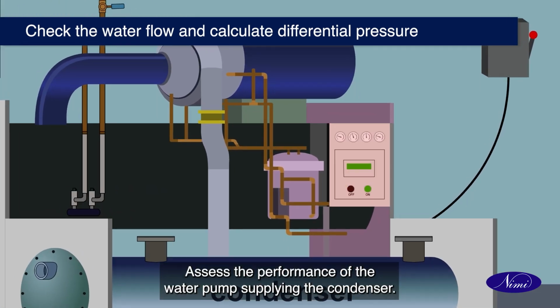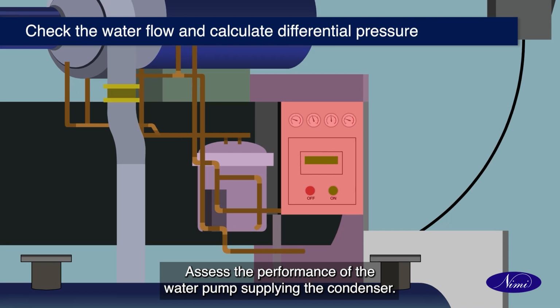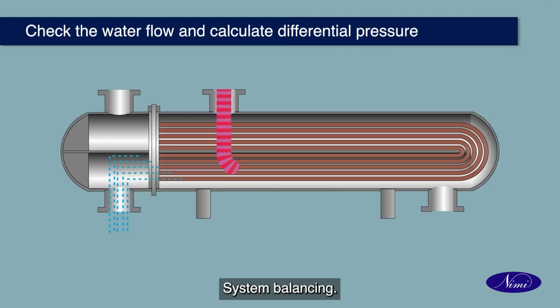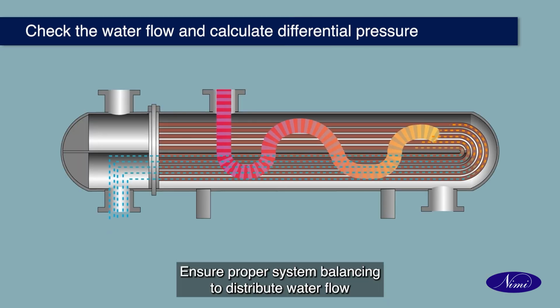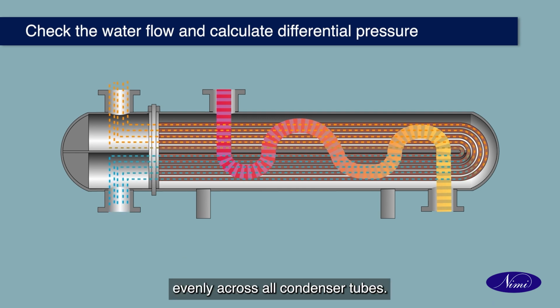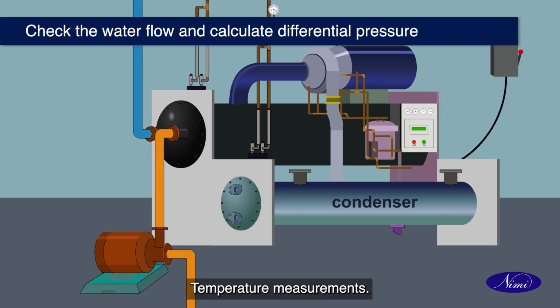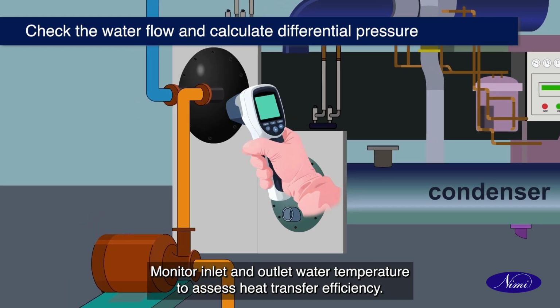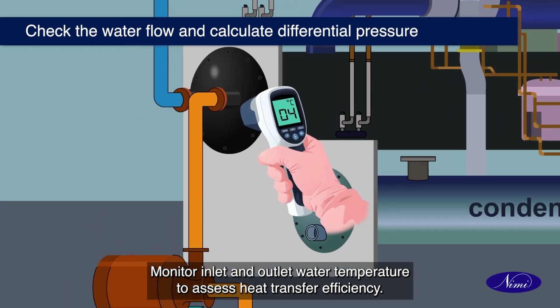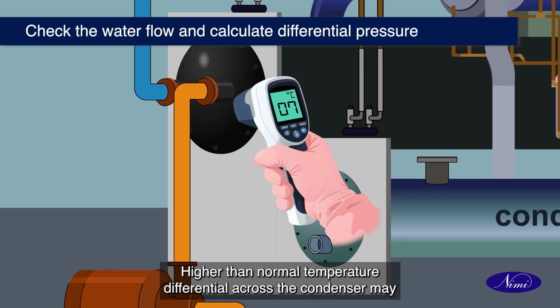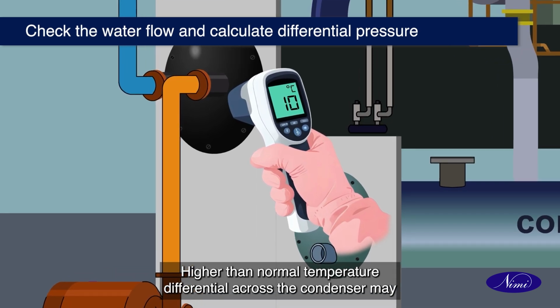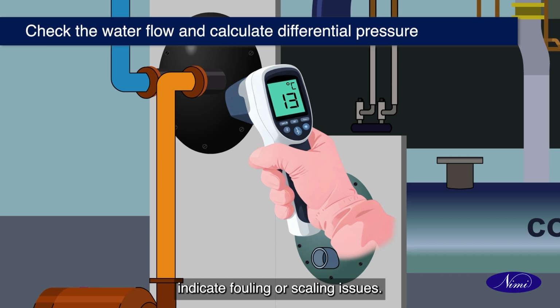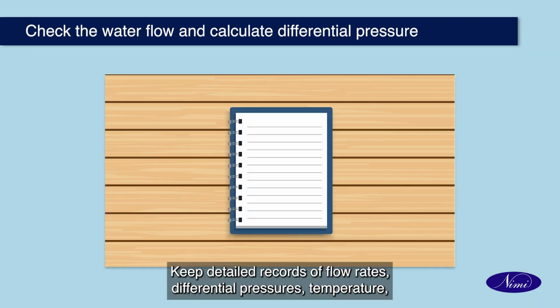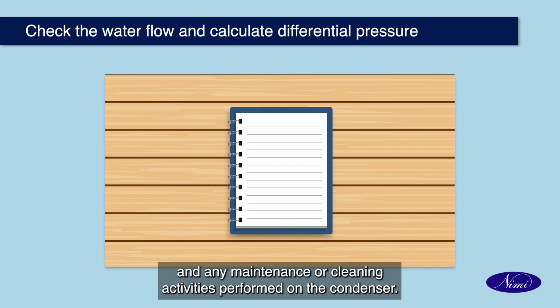Pump performance. Assess the performance of the water pump supplying the condenser. System balancing. Ensure proper system balancing to distribute water flow evenly across all condenser tubes. Temperature measurements. Monitor inlet and outlet water temperature to assess heat transfer efficiency. Higher than normal temperature differential across the condenser may indicate fouling or scaling issues. Record keeping. Keep detailed records of flow rates, differential pressures, temperature, and any maintenance or cleaning activities performed on the condenser.